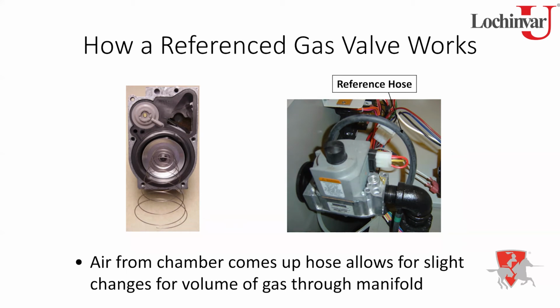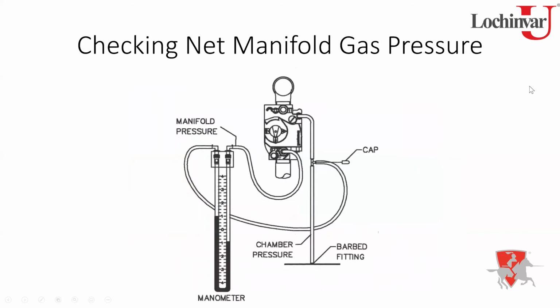Now, how much pressure should we have on that air side? Well, what we're going to look at is how we measure this. If you've got a manometer that has two connections on it, it's really easy to do. You hook up to the outlet of your gas valve, and then you hook up to that air hose that's going down to that deck. You're looking for the difference between those two pressures, and that's called the net manifold.